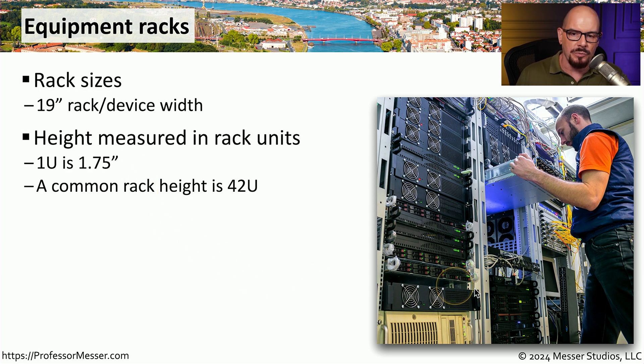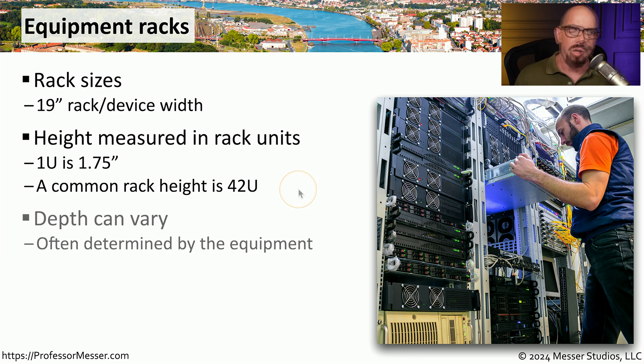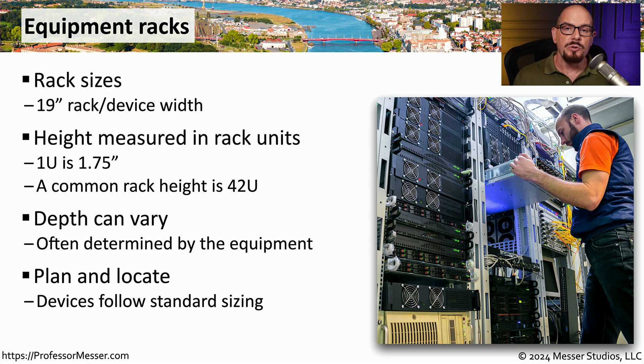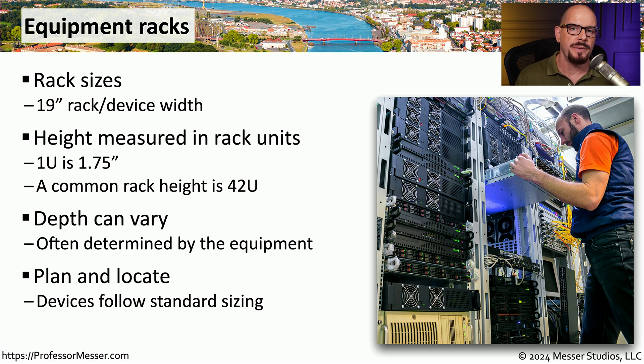Most racks, like the ones we see here, are generally about 42U in height. Although the width is standardized, the depth of these racks can often vary. There might be racks that are very shallow, or others that might support a much longer piece of equipment. Fortunately, most devices follow this standardized form. We know that if we're receiving a piece of equipment that is rack mountable, it will most likely be 19 inches wide. We'll just need to make sure that we have a rack that is deep enough to handle that particular piece of equipment.